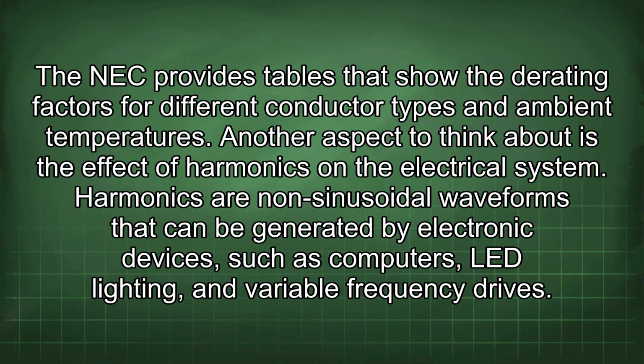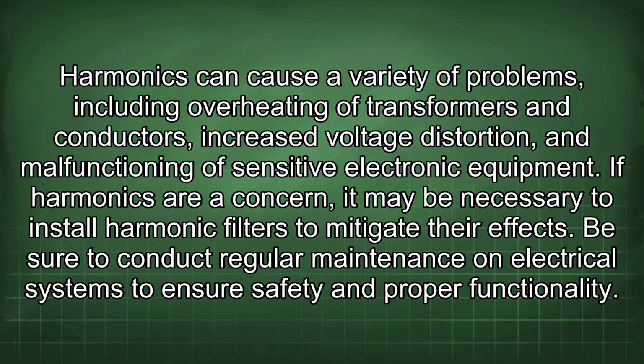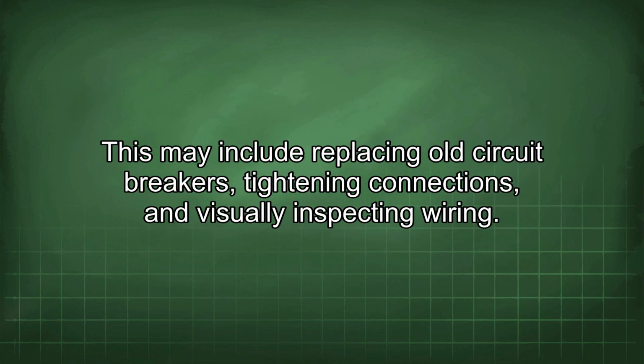Another aspect to think about is the effect of harmonics on the electrical system. Harmonics are non-sinusoidal waveforms that can be generated by electronic devices such as computers, LED lighting, and variable frequency drives. Harmonics can cause a variety of problems, including overheating of transformers and conductors, increased voltage distortion, and malfunctioning of sensitive electronic equipment. If harmonics are a concern, it may be necessary to install harmonic filters to mitigate their effects. Be sure to conduct regular maintenance on electrical systems to ensure safety and proper functionality. This may include replacing old circuit breakers, tightening connections, and visually inspecting wiring.